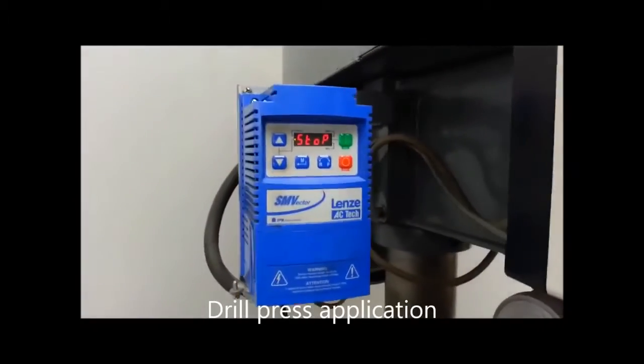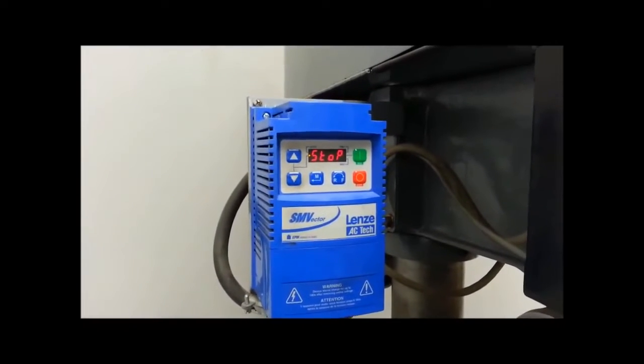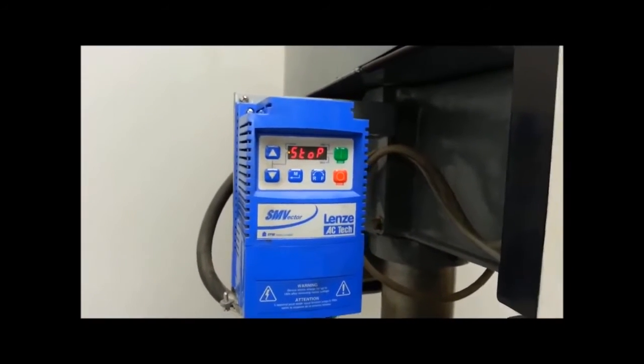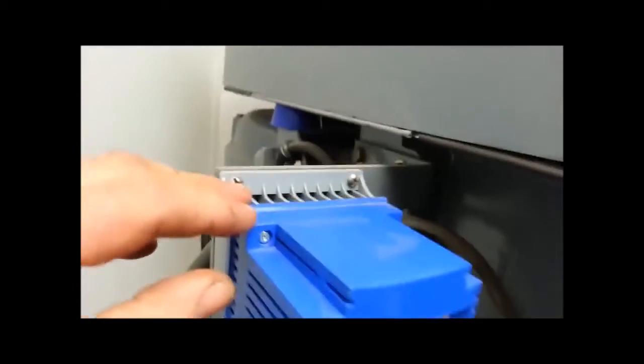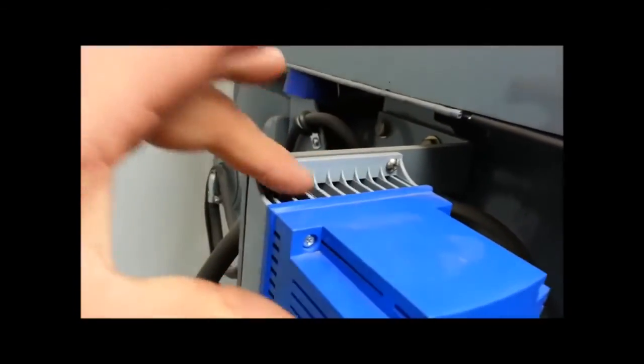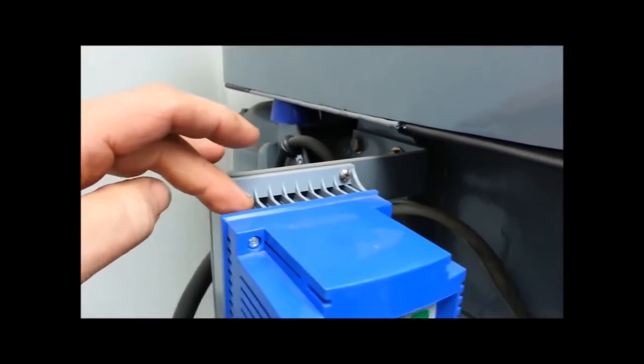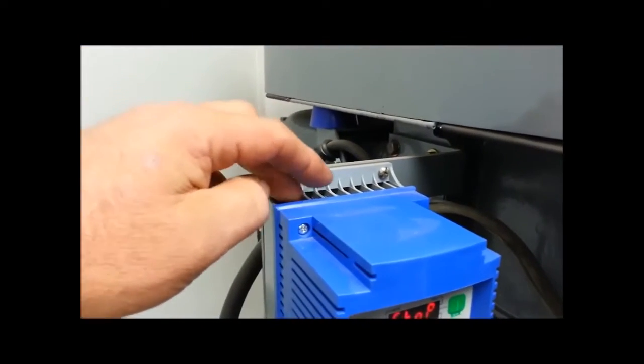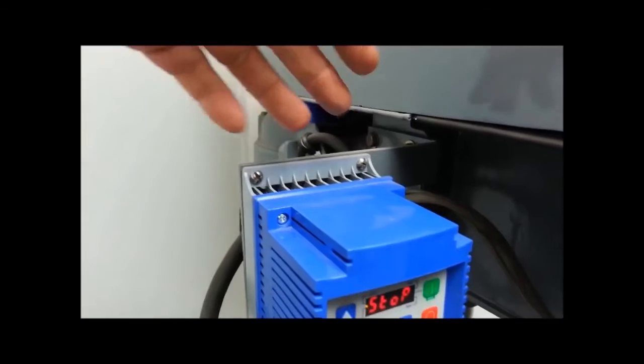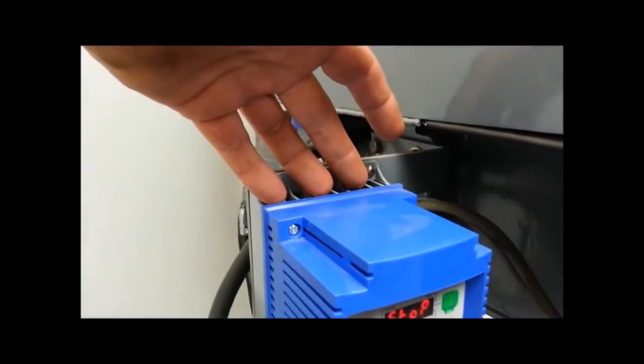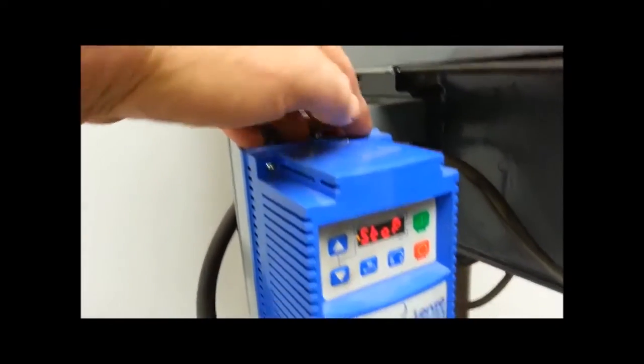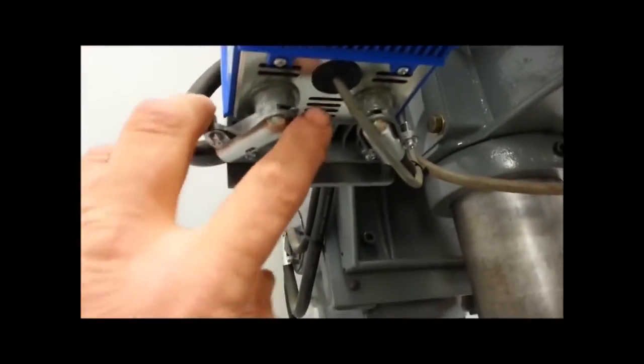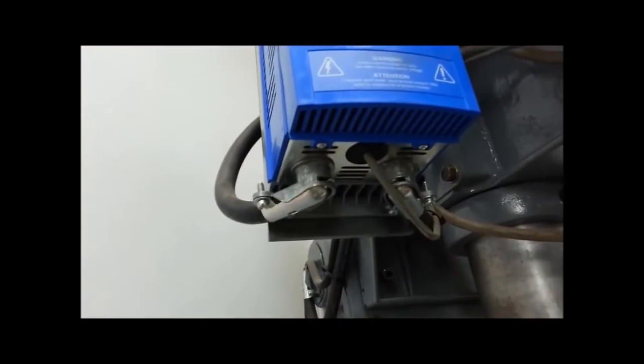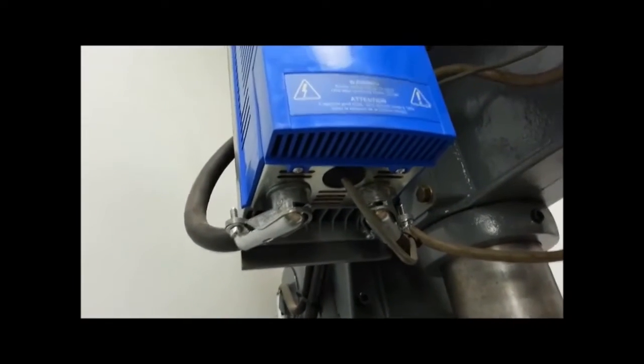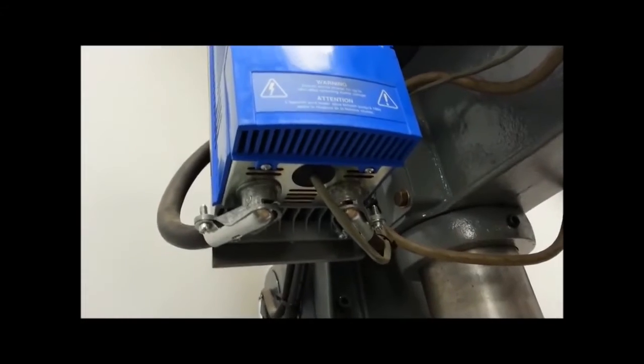Now I like these SM Vector drives, for a couple of reasons. The housing on these is nice, nothing exposed in the back. This is just an aluminum finned heat sink to allow the heat out. And if metal chips or anything get down there, there's no electronics that are going to get hurt. And also they've got a wiring box built right into the bottom here, so you don't have any open wiring like some of the cheap little Ticos and some of the little Chinese things.